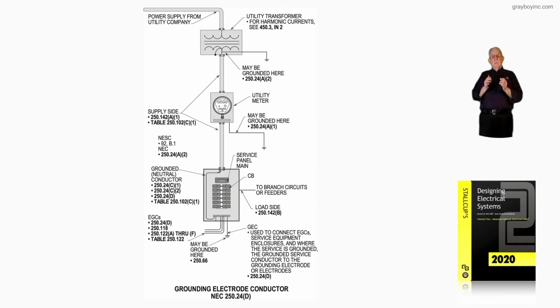But now here, notice the grounding electrode conductor at the service equipment. It grounds that grounded bar, where the grounded conductor, which may be a neutral too, from the transformer and meter connects to that common bar, which is bonded to the enclosure, and all equipment grounds and neutrals connect there. And you see the sections there that you need to review to get a handle on that, for it to be strong in your mind. And then you notice the grounded neutral conductors listed there, the sections we need to look at that we've already covered with you.